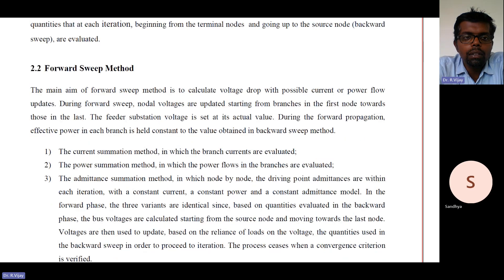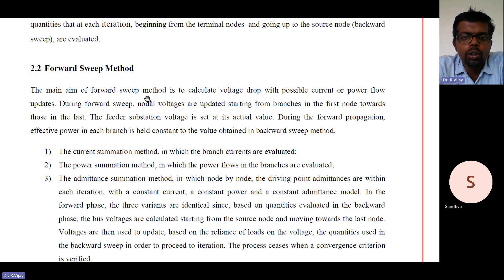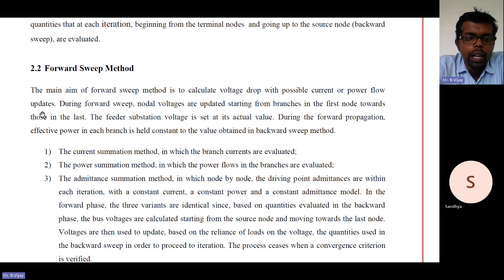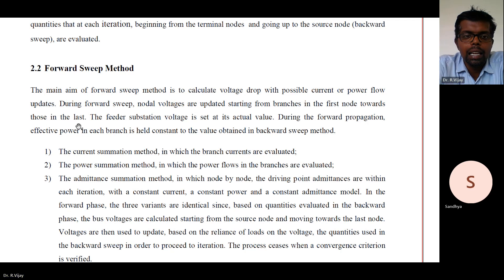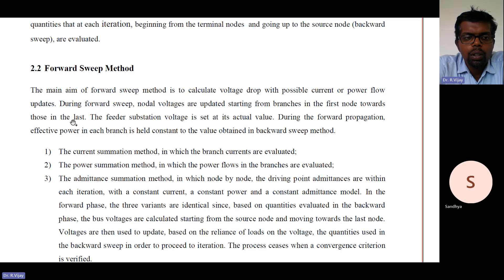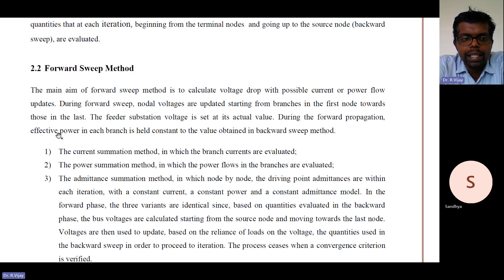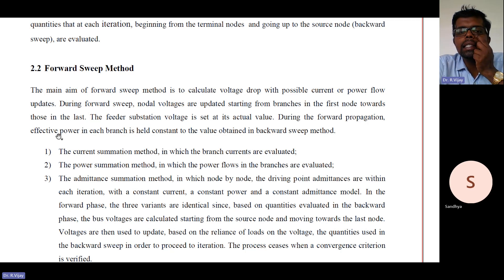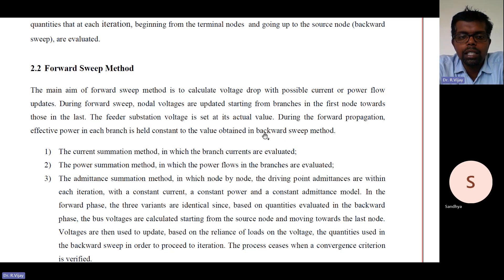Coming to the forward sweep method: the main aim of the forward sweep method is to calculate the voltage drop with the possible current or power flow updates. During the forward sweep, nodal voltages are updated starting from the branches at the first node towards those at the last node. The feeder substation voltage is set to its actual value. During forward propagation, effective power in each branch is held constant to the value obtained in the backward sweep.